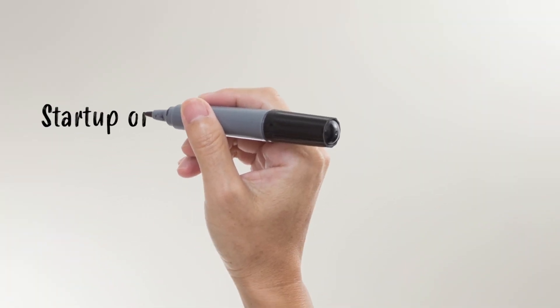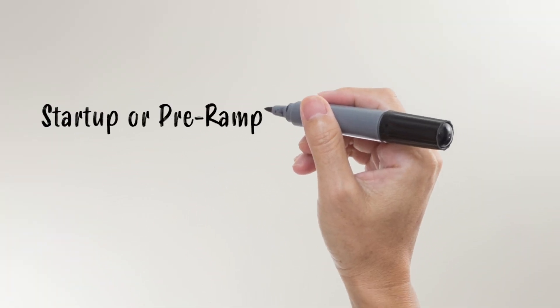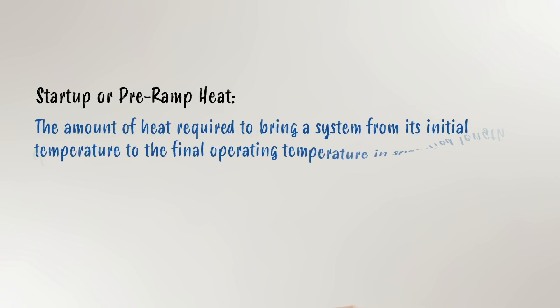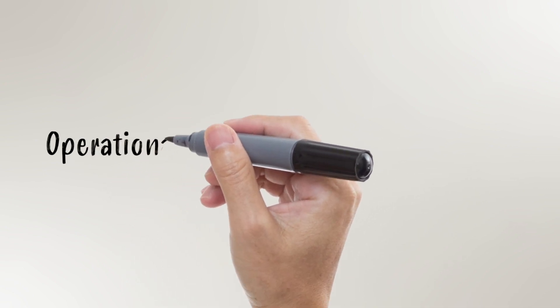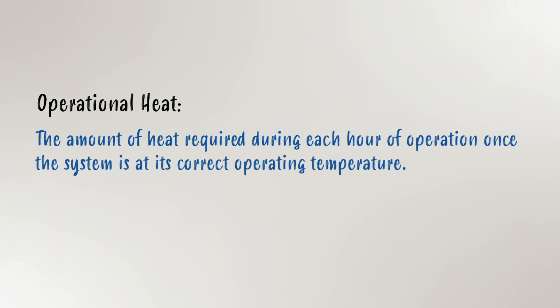First, I want to talk about the difference between startup and operational heat requirements. Startup, or preheat, is defined as the amount of heat required to bring a system from its initial temperature to the final operating conditions in a specified length of time — think of it like preheating your oven before you bake a batch of cookies. Operational heat is defined as the amount of heat required per unit of time, usually an hour, once the system is at its specified operating temperature. The majority of the energy is on the operational side, so our focus will be determining the kilowatts required on this portion of the equation.